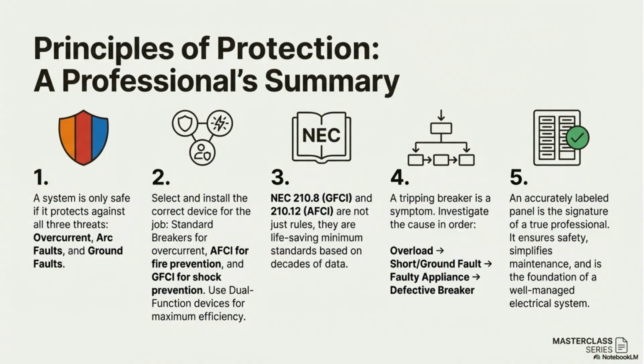In summary, a truly safe system protects against overcurrent, arc faults, and ground faults. Select the correct devices for each job, recognizing that NEC standards are minimum requirements. Remember that a tripping breaker is a symptom. Investigate the cause in order of overload, short/ground fault, faulty appliance, and defective breaker. Finally, an accurately labeled panel is the foundation of a well-managed electrical system.